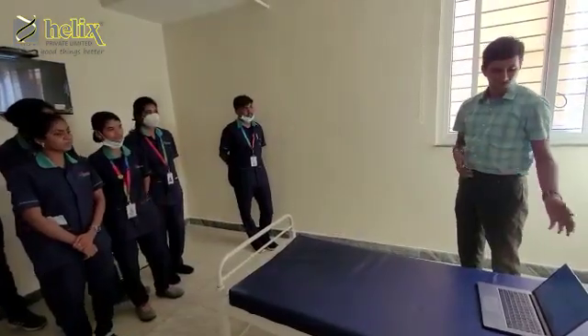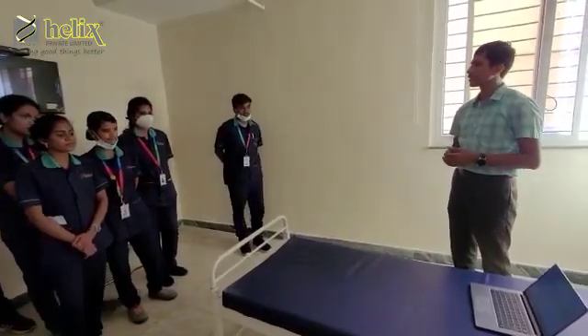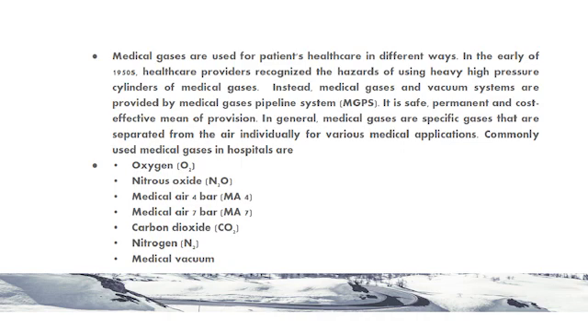Let us see what are the major medical gases that we are using. First is oxygen. Oxygen is coated with white color throughout the hospital — both outlets as well as the copper pipes are coated with white for easy identification.